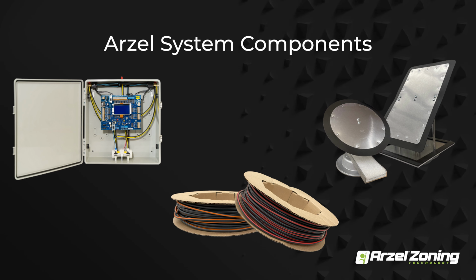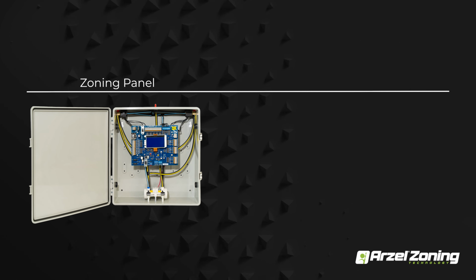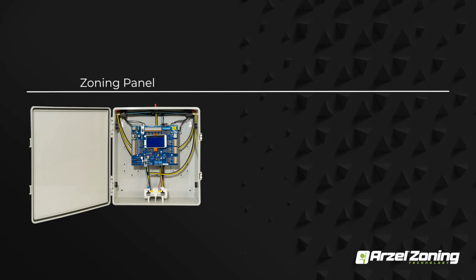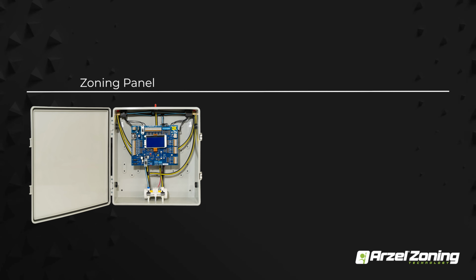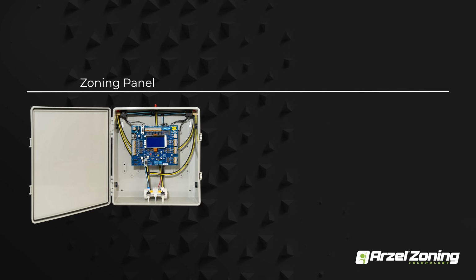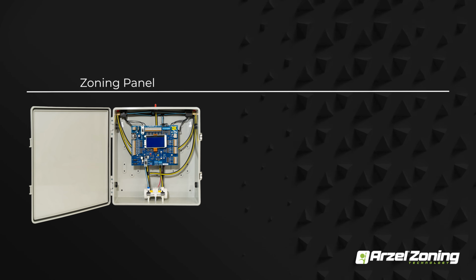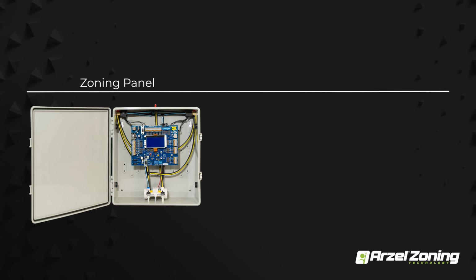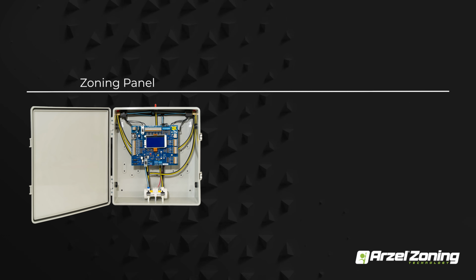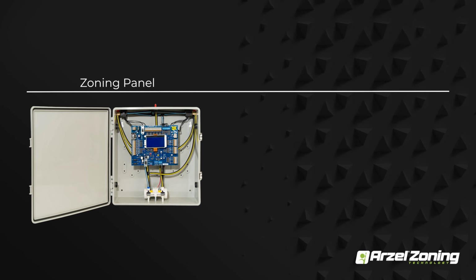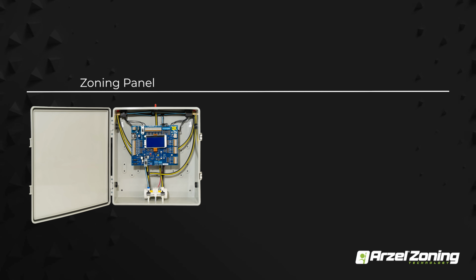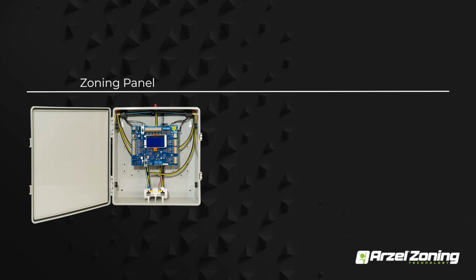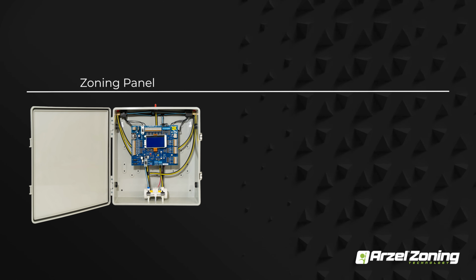So with our system, there's essentially three main components. You're going to have your zoning panel. So whichever panel you guys decide to go with, we typically recommend our Heat Pump Pro as our go-to panel for anything 4 zones or less. This will work for any piece of equipment, so any 24-volt controlled piece of equipment out there, from single stage all the way through dual fuel applications. And it'll be able to do that for you guys with just a single stage heat cool thermostat.